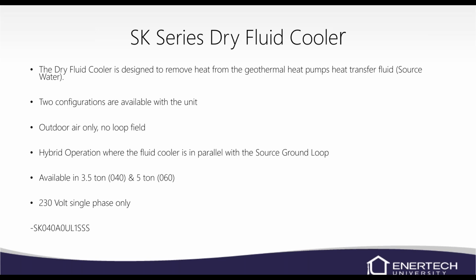It is available in 3.5 and 5 tons, so the 040 and the 060, and it's 230 volt single phase only. If you look down at the model nomenclature, SK 040, really the only option that you have on this is where the L is located. That's either going to be a flow switch with a pump that's already on site, or like a flow center pump, or you can get the load pump for it if you're not going to use it with a loop field. So you can just pump it from the fluid cooler to the unit itself.